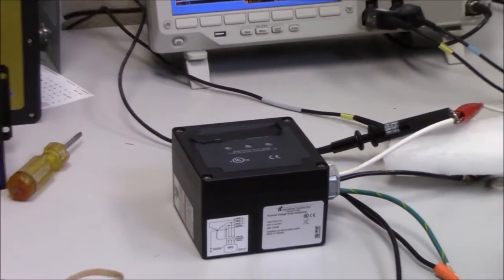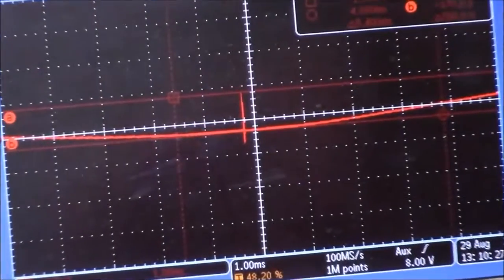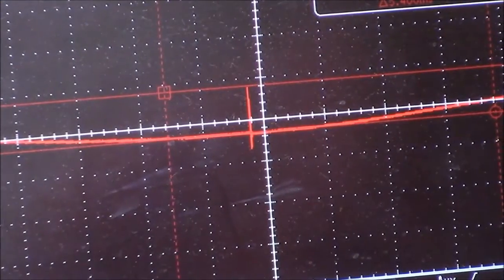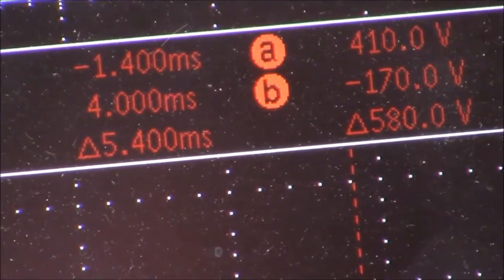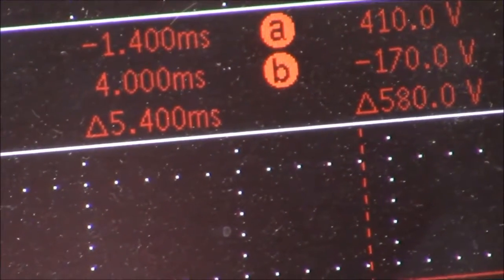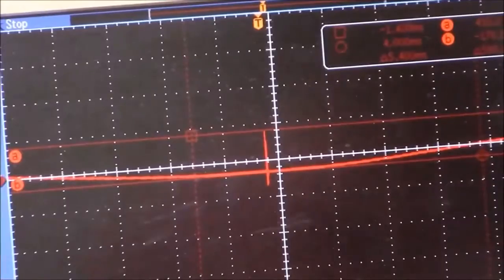Okay, we're staying with the 100 kilohertz ring wave. The last one was 900 volts. This one does a little bit better job on the ring wave where it's at about 580 volts. So this is more of a hybrid type of unit rather than just a straight metal oxide varistor.